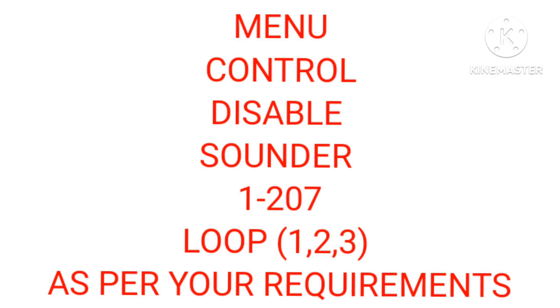To disable sounders in the individual panel, first go to Menu, then Control, then Disable, then Sounders. Then enter the parameters — 1-207 — then select the loop. Put in whichever loop is required, for example loop 1 or 2.